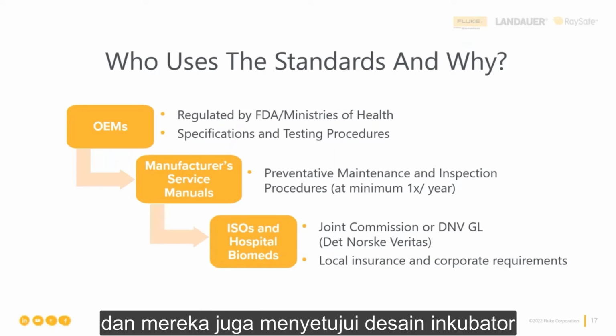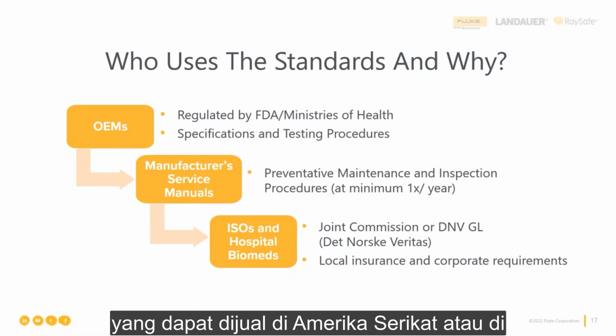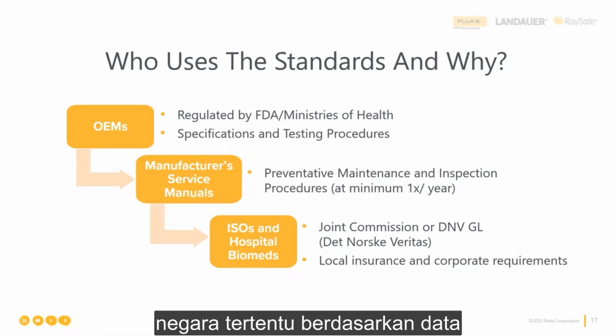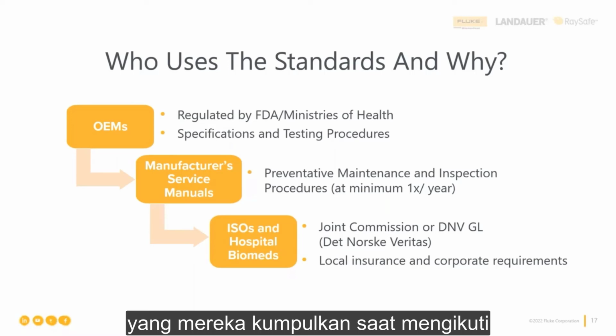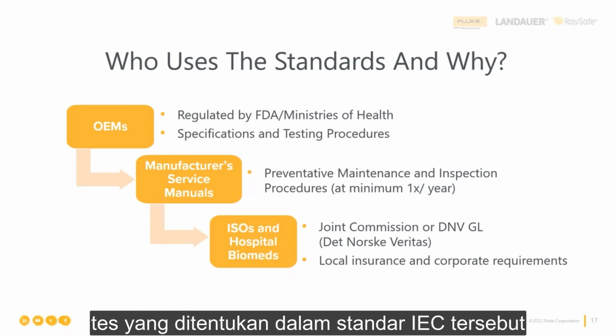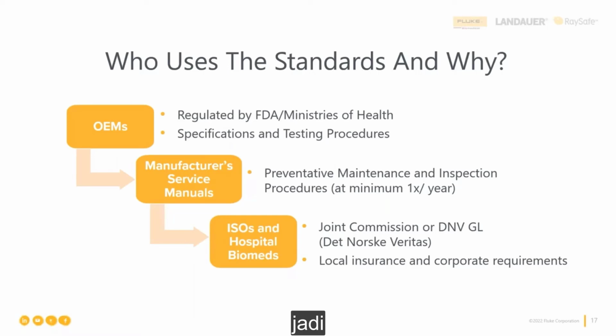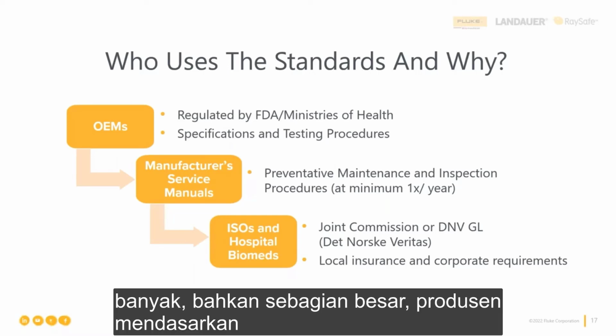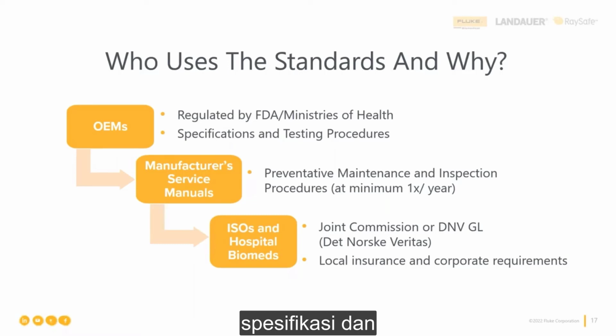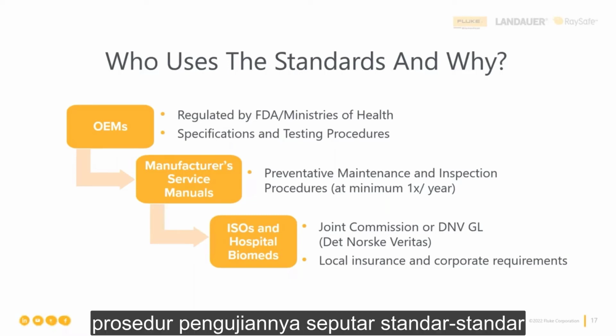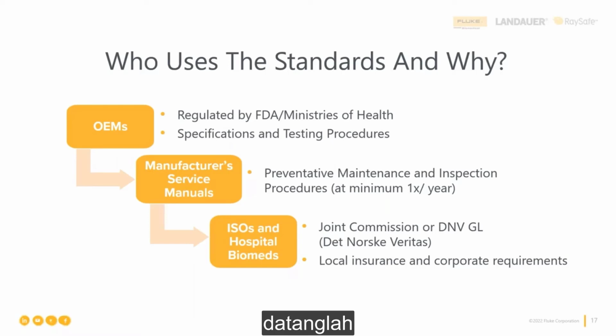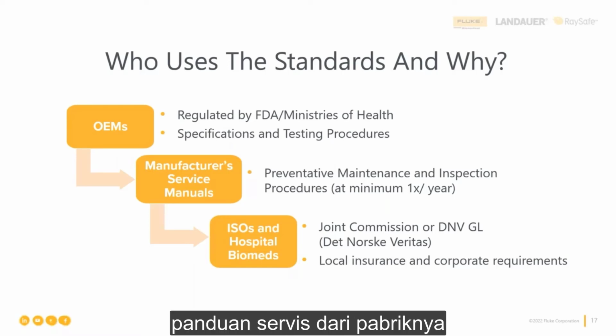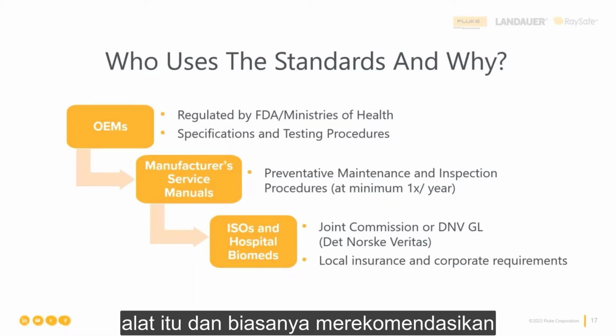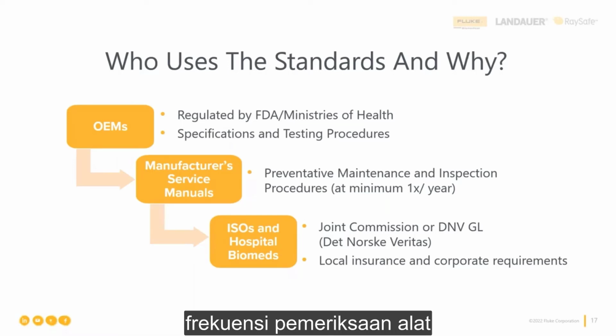outside of the US. And they also approve incubator designs that can be sold in the USA or in specific countries based off of the data that they collect when following the prescribed tests in those IEC standards for incubators. So many, if not most, manufacturers base their specifications and their testing procedures around the standards. And from them comes the manufacturer's service manual. A manufacturer's service manual will contain procedures that are specific to the maintenance and performance of that device and typically recommend an inspection frequency.